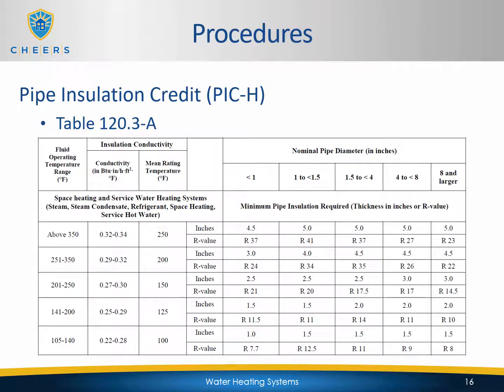And here is table 120.3-A. If we look at this table, it gives various ranges of temperature that's going to be moving through various pipes, as well as pipe diameters, and then the required R value or inches of insulation. Because we are dealing with domestic hot water, it's going to be an average of about 120 degrees. That's the recommended temperature. So if we look on the chart in the very first column on the left, we're going to want to go all the way down to the bottom where it's 105 to 140. All of these DHW systems should fall within that range.